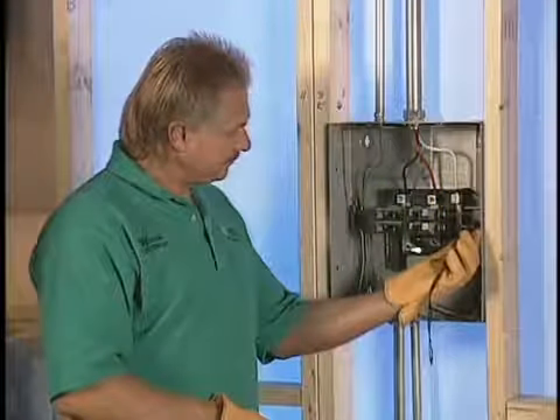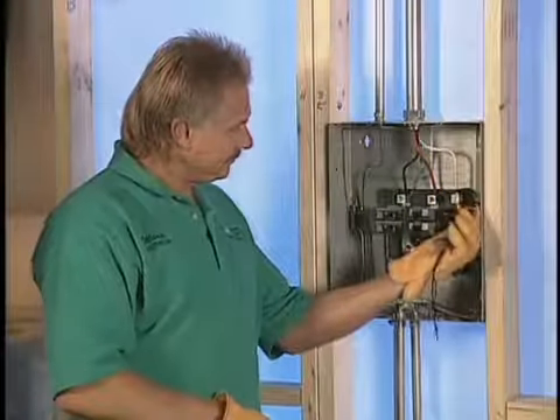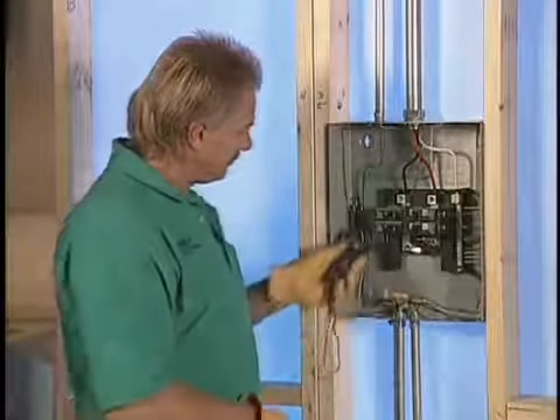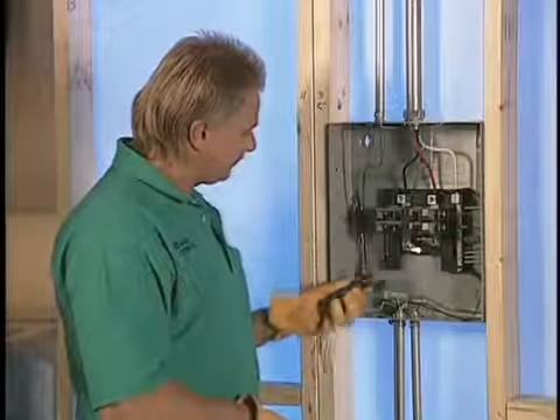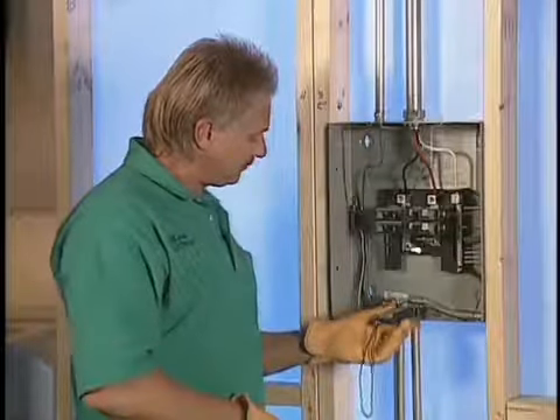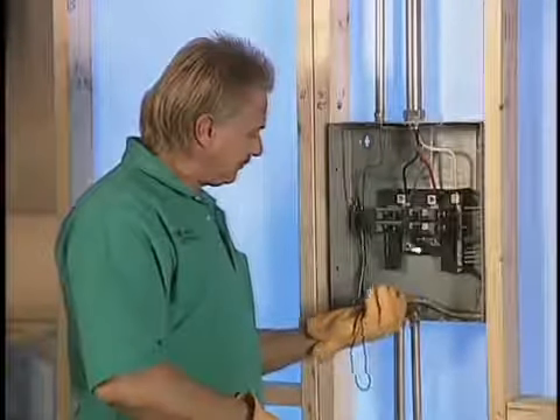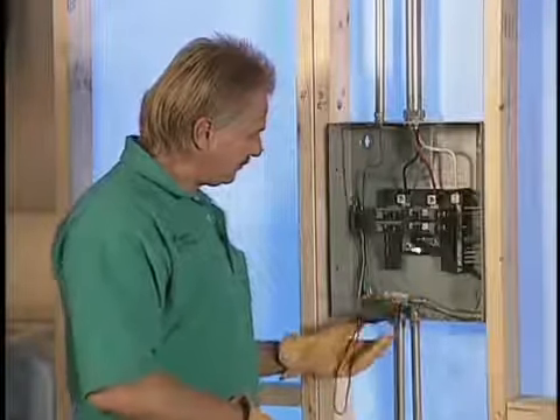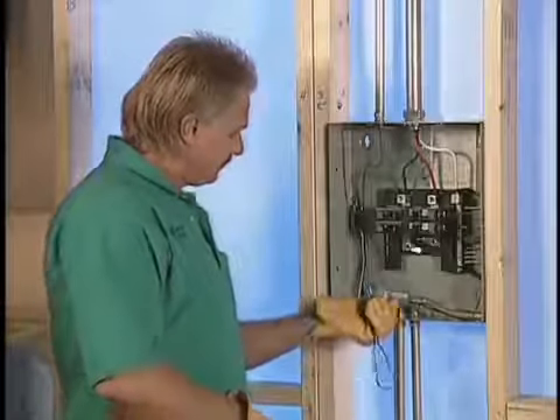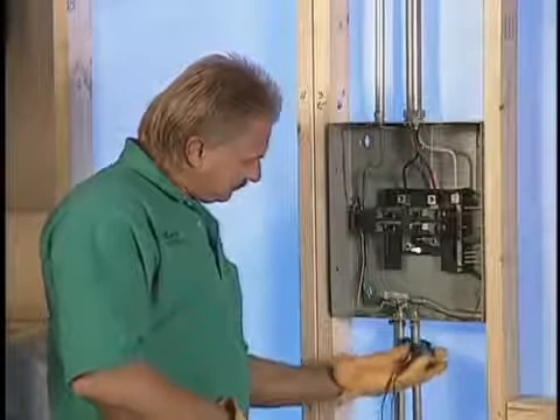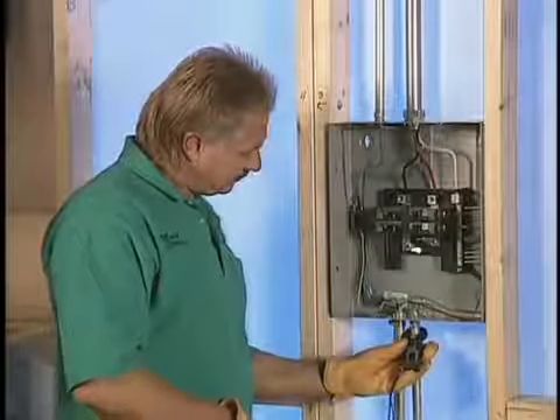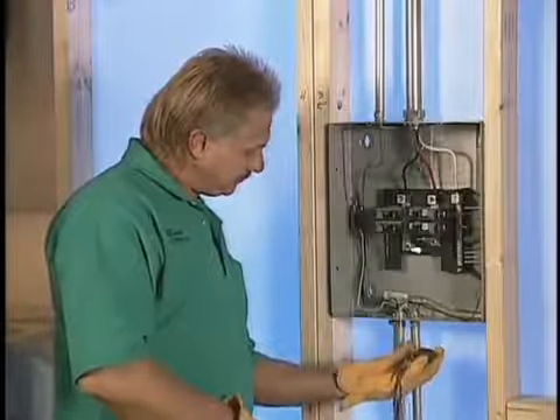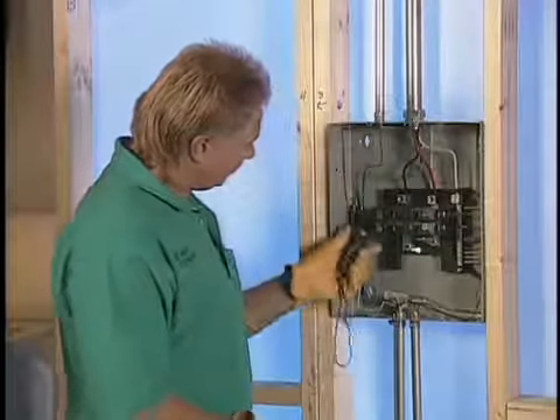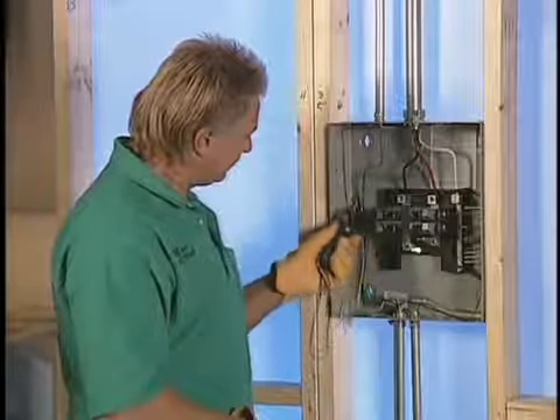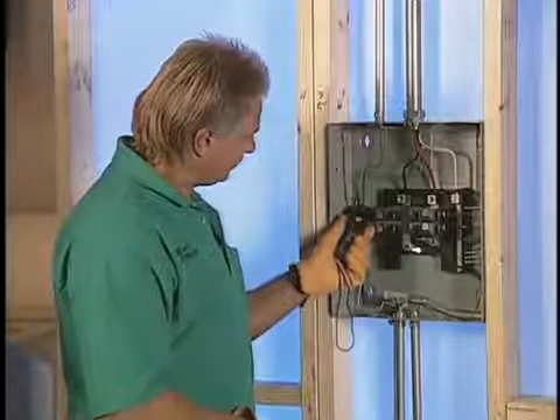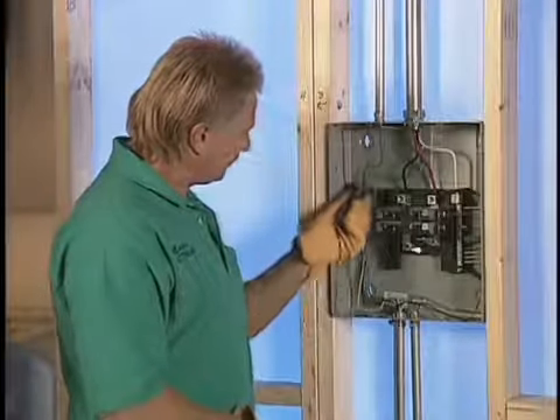To resume our search for net current circuits, you will need to clamp around each group from every conduit and record your measurements. You can find a suggested form in your handout. To obtain the measurements, clamp around each group. Sometimes it is easier to clamp around the conduits outside the box. Once you've found a conduit group with net current, you can trace it out into the building. If you want to know what is causing the net current situation, you can measure the hots and neutrals in the panel box.